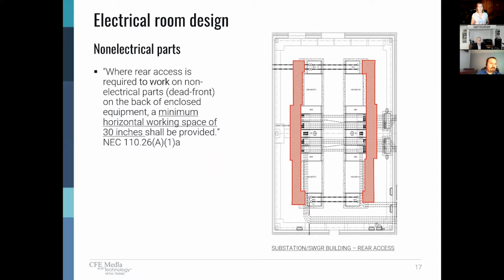Now, sometimes, depending upon the manufacturer requirements, gear will require rear access. Sometimes this is to get to non-electrical parts, for example, replacing an air filter on the back that needs to be changed on a recurring basis. If that's the only reason that we need access to the rear of the gear, then code requires that we have a minimum of 30 inches horizontally behind the gear. But if there are needs to get back there for inspection or for termination of cabling and the like, then the clearances that we previously discussed out of NEC 110.26(A)(1) would apply, similar to the front of the installation.